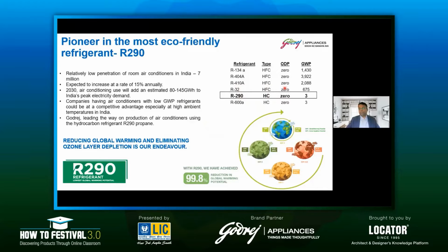You can see the global warming potential on the right-hand chart. Compared to refrigerants like R32, which is what's primarily available in the market at 675, we have R290, which is only 3. So when you're specing or designing a product for your clients, keep in mind India is also signatory to low carbon emission targets by 2060. You can look at all sustainable products in terms of low global warming footprint. R290 is the refrigerant with a GWP of only 3.